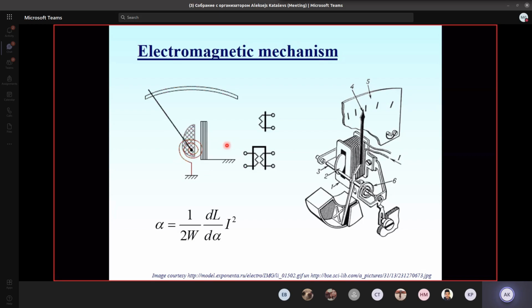The core, a piece of magnetic metal, is attracted inside the coil. And as the magnetic field in the coil is proportional to the current, and the magnetization of the core is proportional to the magnetic field, it means it's proportional to the current too, so the deflection angle is totally proportional to the square of the current. So the electromagnetic mechanism is not linear.